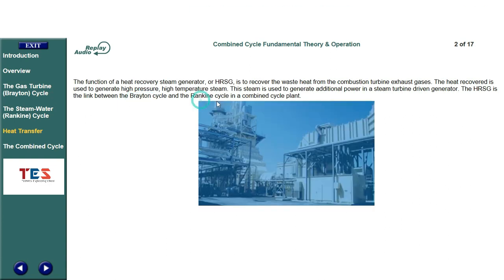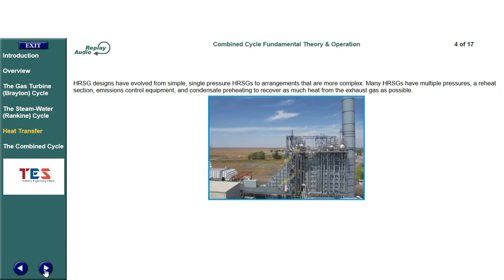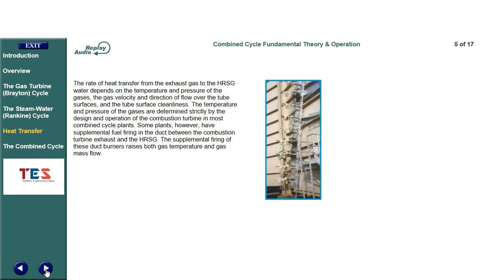HRSG designs have evolved from simple, single-pressure HRSGs to arrangements that are more complex. Many HRSGs have multiple pressures, a reheat section, emissions control equipment, and condensate preheating to recover as much heat from the exhaust gas as possible. The rate of heat transfer from the exhaust gas to the HRSG water depends on the temperature and pressure of the gases, the gas velocity and direction of flow over the tube surfaces, and the tube surface cleanliness.